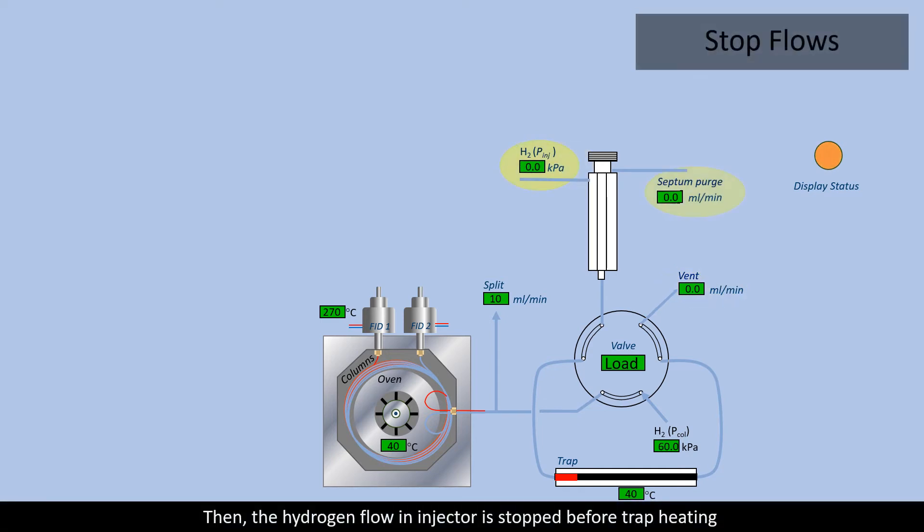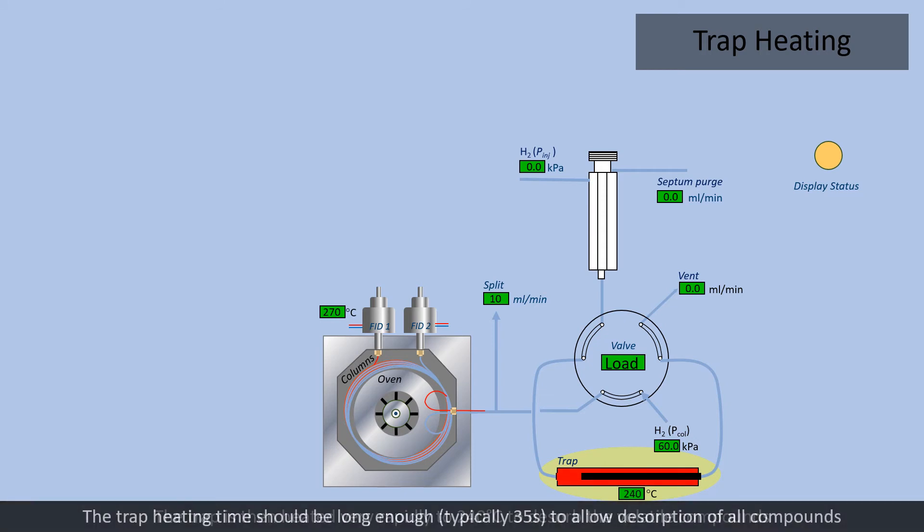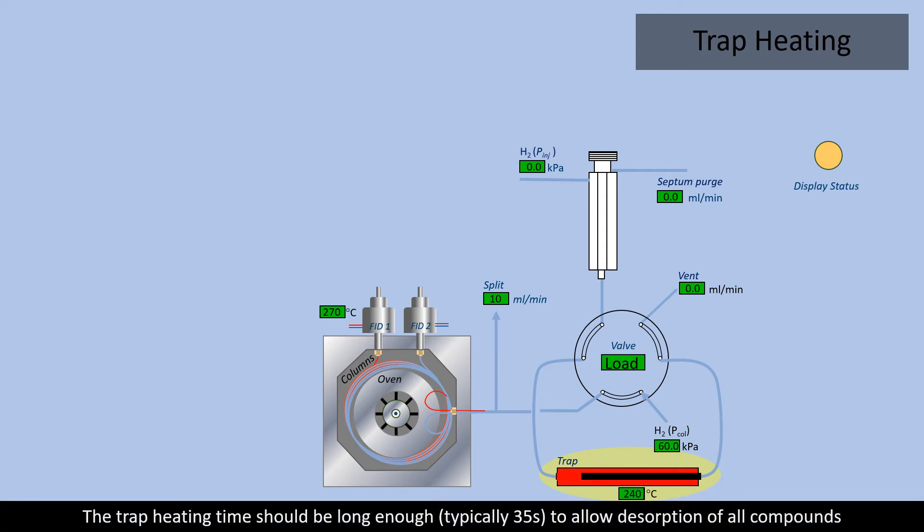Then, the hydrogen flow in injector is stopped before trap heating to prevent the elimination of volatile molecules to the vent. The trap is then heated very rapidly to 240 degrees to desorb the volatile compounds. The trap heating time should be long enough, typically 35 seconds, to allow desorption of all compounds.